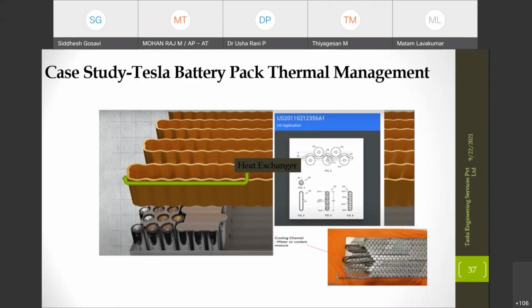For example, in a cylindrical cell, the temperature variation across the cross section, longitudinal, radial, everything should be within 1 degree Celsius. That is the intra-cell temperature gradient. The inter-cell gradient depends on the structure, and parallel branching of the cooling pipes helps minimize it.